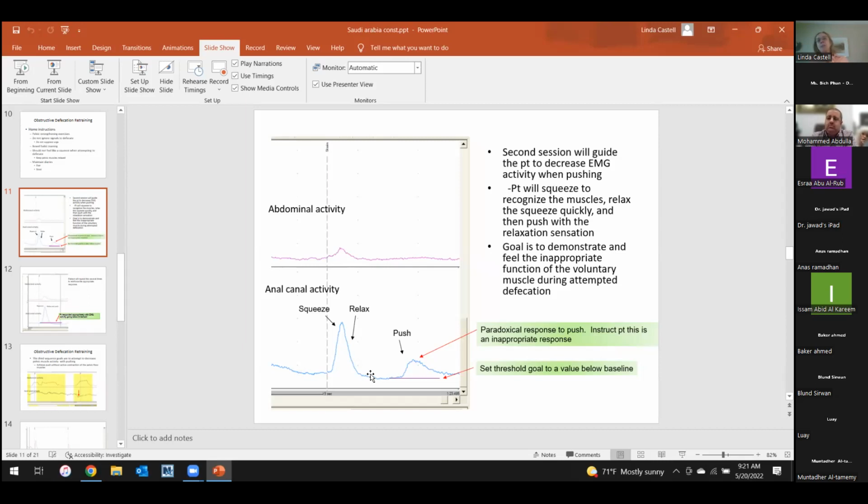So what I do, and I'm not sure this is optimal, is pass my catheter so all sensors are in the rectum. I do my rectal baseline there, and I hope that everything's pretty stable. First I do a baseline outside the body at atmospheric pressure, so all the pressures on all 23 sensors are the same.